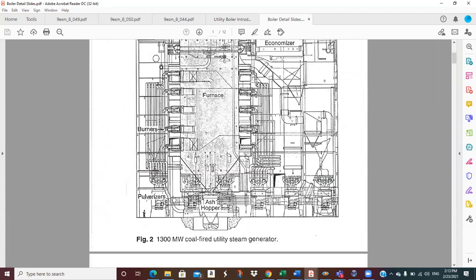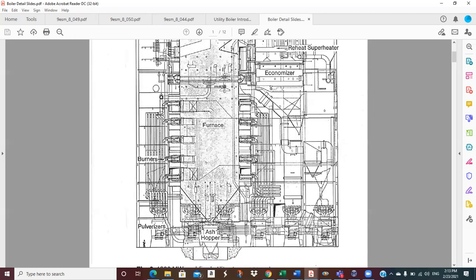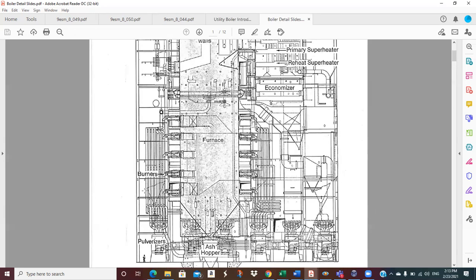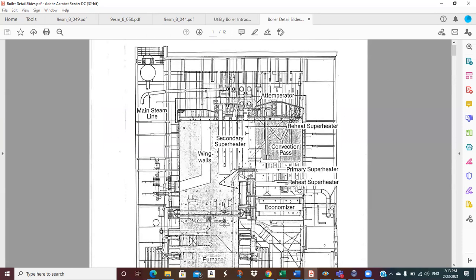Now, 1,300 megawatts, that's about as big as a unit's going to be. And so, goodness gracious, look at all of this stuff. And we'll work our way through, there's just a whole lot to look at. This is your main steam drum up here, your main steam line. They're not showing all the pipes, but the saturated steam comes out of the drum. And where does it go first? It goes to the primary superheater, so it comes all the way over here. It picks up energy, and then it goes back to the secondary superheater because it's closer to the furnace, so it's higher temperature. When it comes out of the secondary superheater, that's maximum temperature. Off it goes to the turbines.